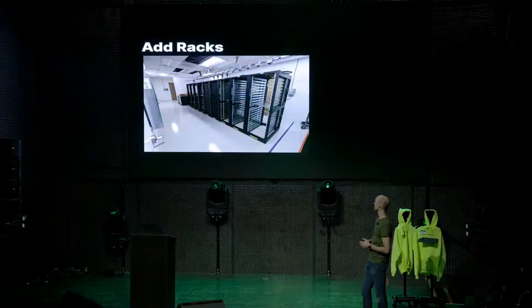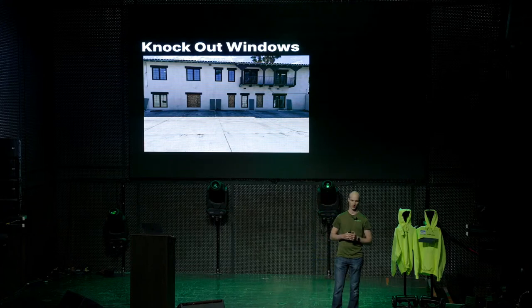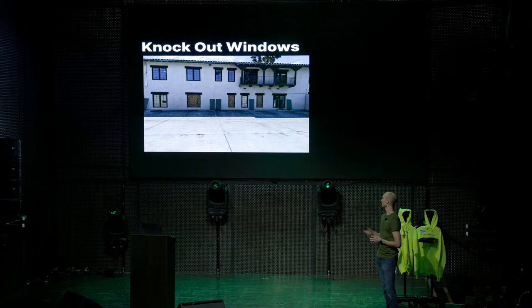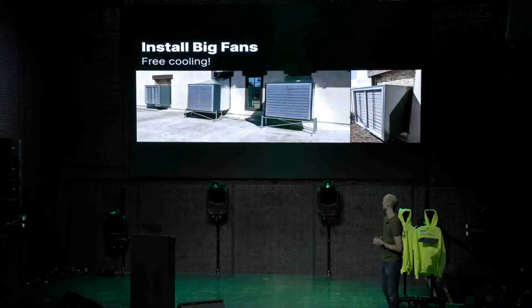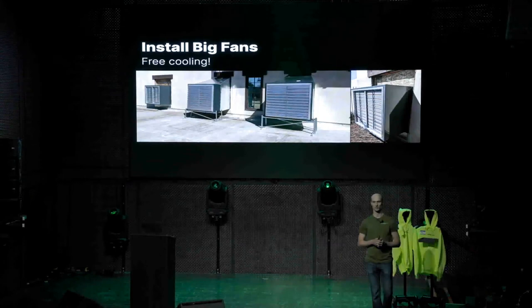In this room we added a couple of short walls to help with hot-aisle containment, and the racks go in between those walls — 42U racks. We knocked out some windows. Just like in our last data center, we only use fans, no air conditioning. We're in San Diego and can potentially save a ton of money not using AC. We installed some really big fans — 3 horsepower each, doing about 28,000 CFM.